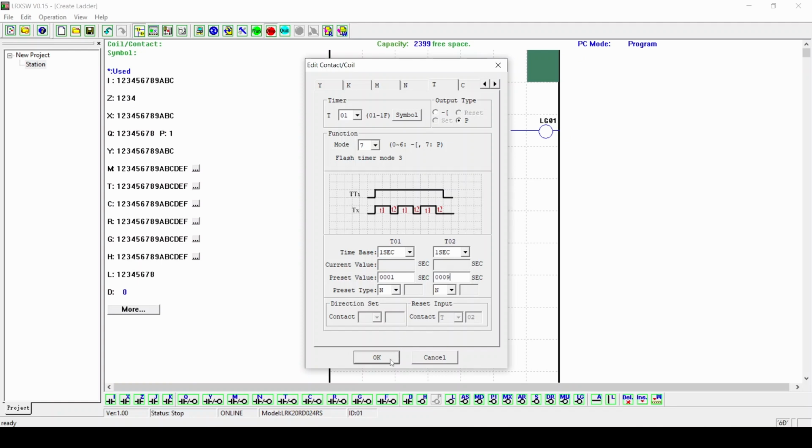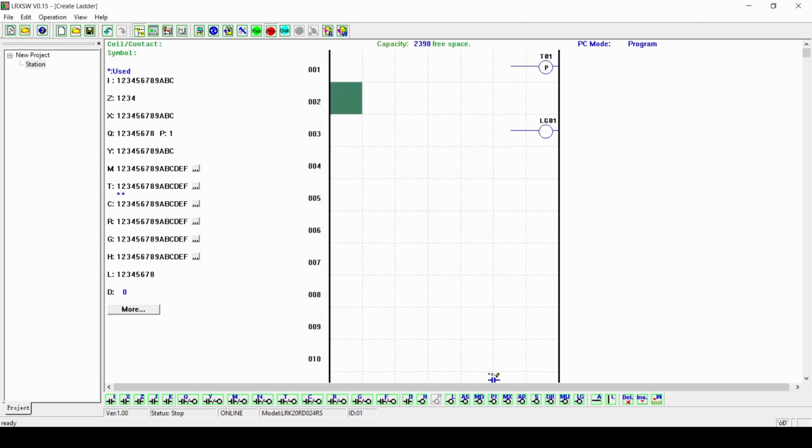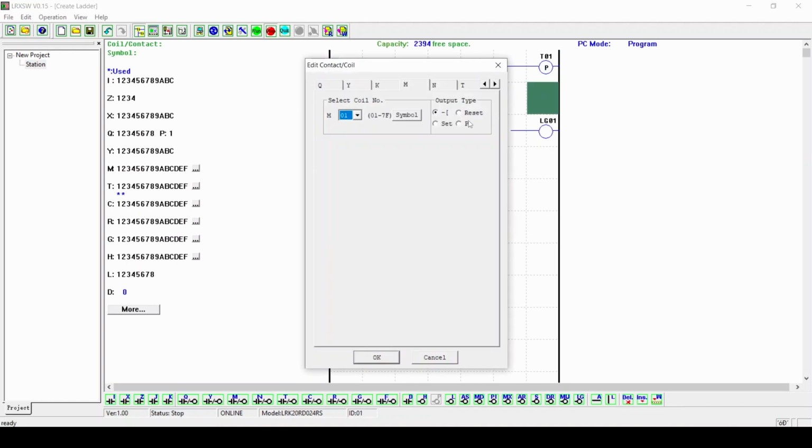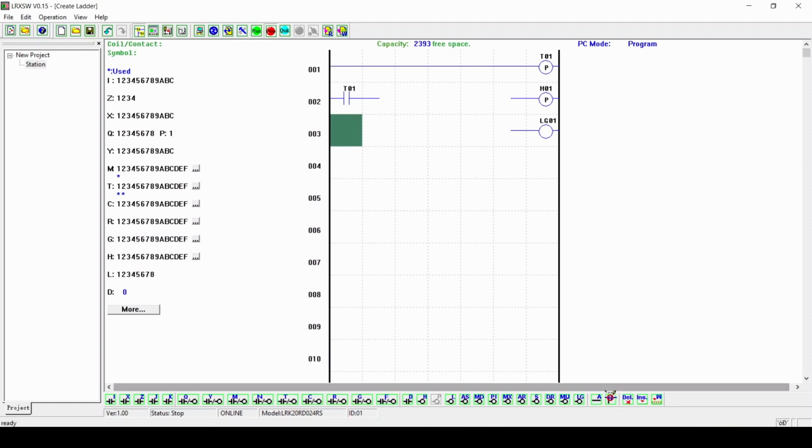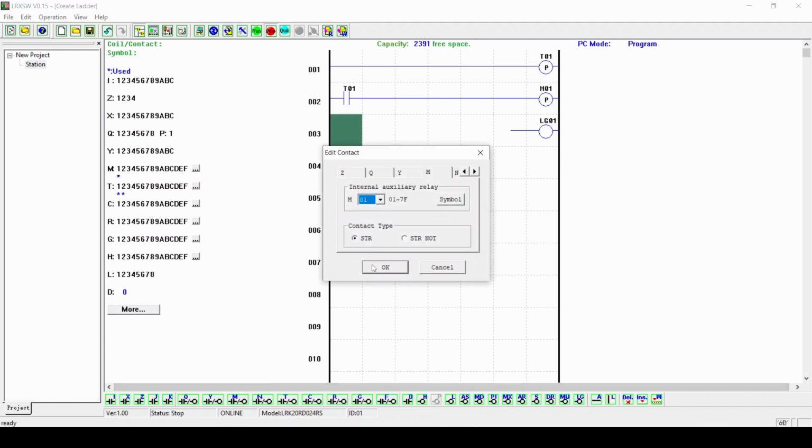Now connect timer T01 to a support marker, for example M01 configured in flip-flop mode. On the next line, connect marker M01 as enable of the LG01 block and reset M01 in parallel. This step allows you to save one record only for each activation of timer T01. The Micro PLC runs extremely fast, and this avoids generating multiple records.